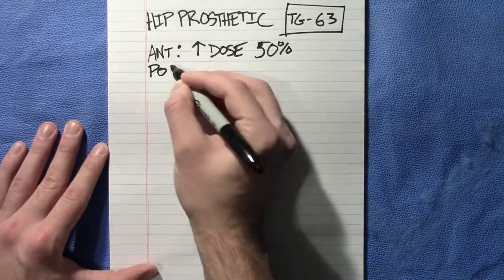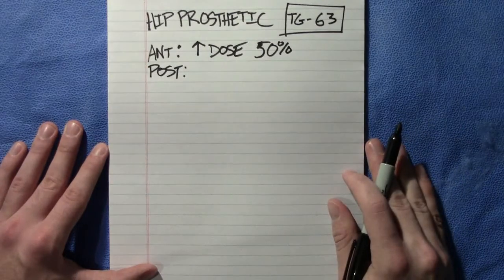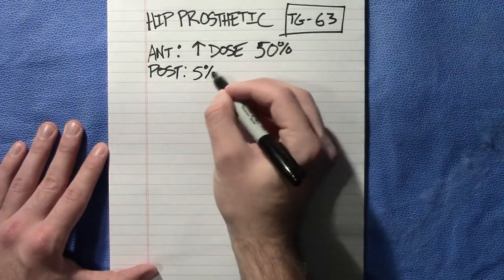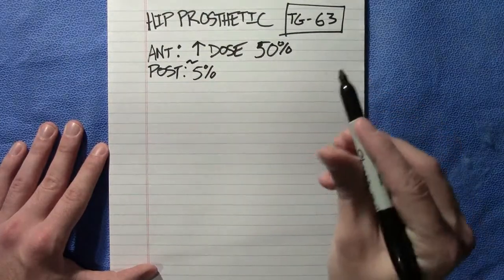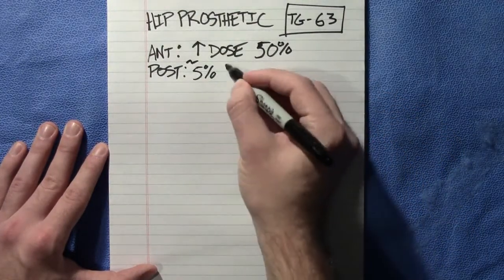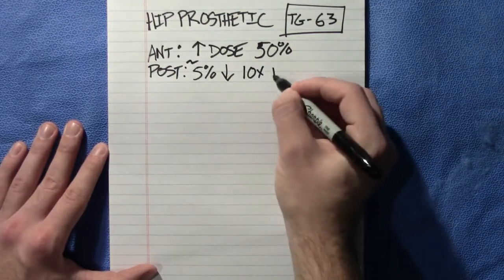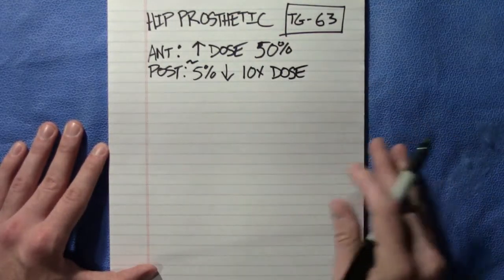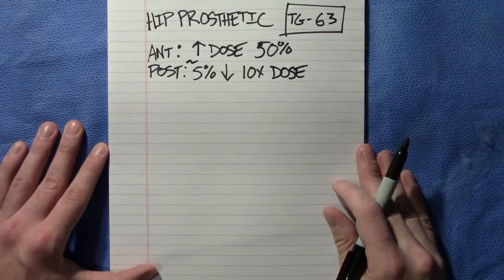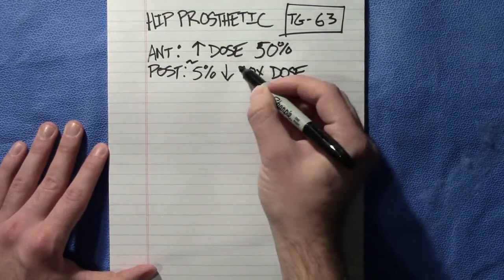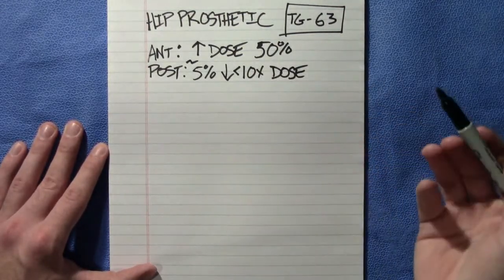Posterior, past the surface, we have approximately a 5% decrease for a 10x beam. This is simply because of the attenuation through the hip prosthetic. That applies to 10x and any beam less than 10x as well.